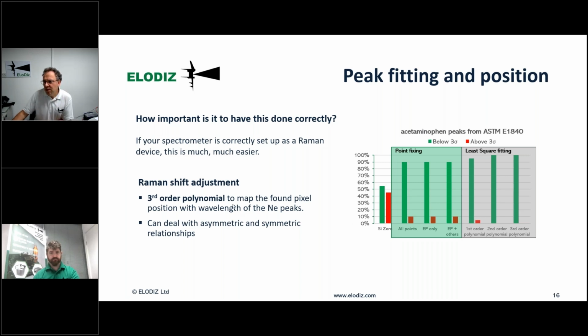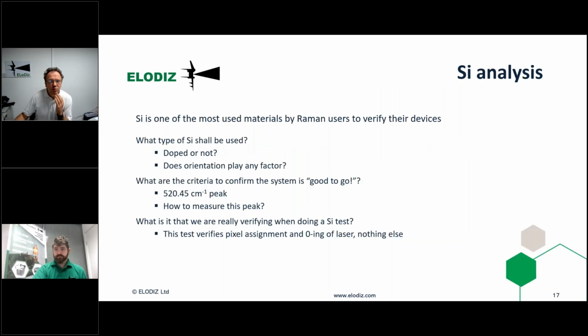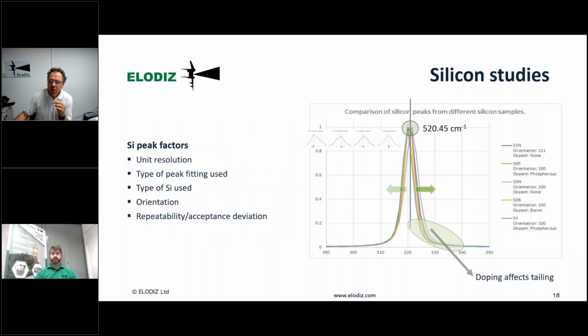Depending on how often you can have the system adjusted, you need to revisit how you make those small adjustments on the system. The protocols start using silicon after the wavelength calibration of the system, but we don't consider that using silicon per se is going to be valid. So we have analyzed what type of silicon. Does silicon introduce an error? Well, silicon is not a unique material. Silicon is often doped with P-type or N-type silicon. So we have analyzed how those affect the center of the peak.